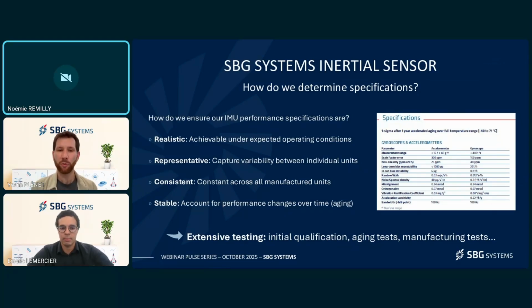So we have some criteria that we use when we make this data sheet, and we need to make sure that it's realistic in the sense that it's achievable under the expected operating conditions. It needs to be representative, so we need to make sure that we take into account the fact that there is some variation between individual IMUs. It also needs to be consistent over time. So here it's not really a question about the individual tests that we do, but making sure that across the time we continue evaluating and auditing our manufacturing tools to make sure that we still meet the same performance requirements that we had at the start.